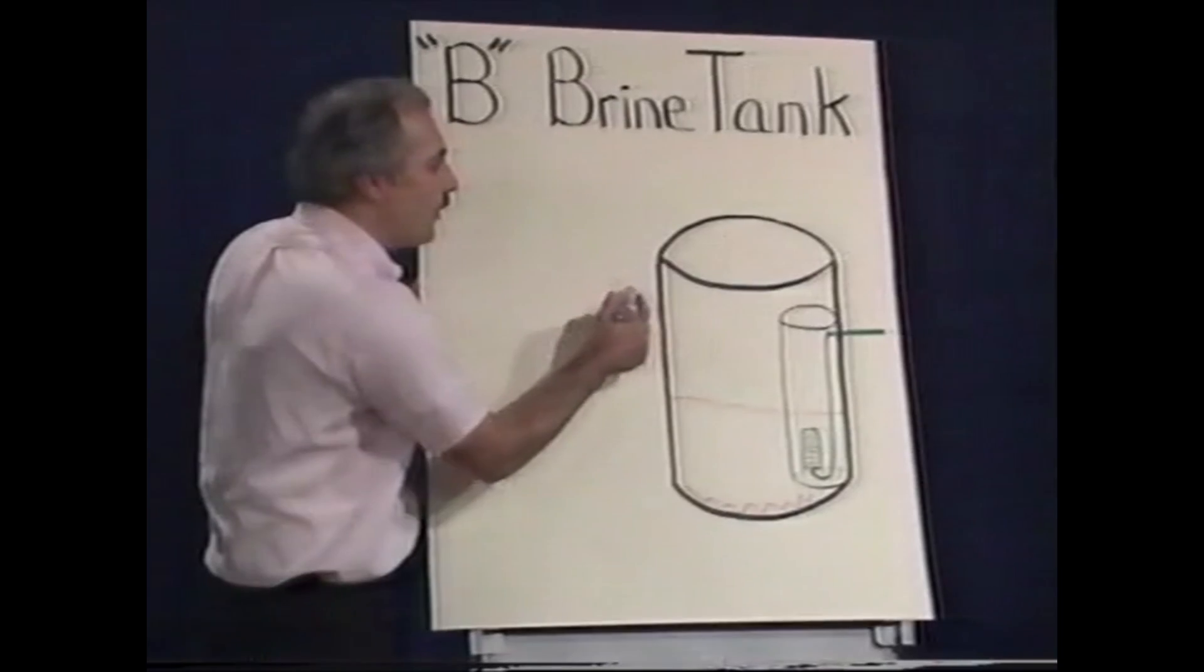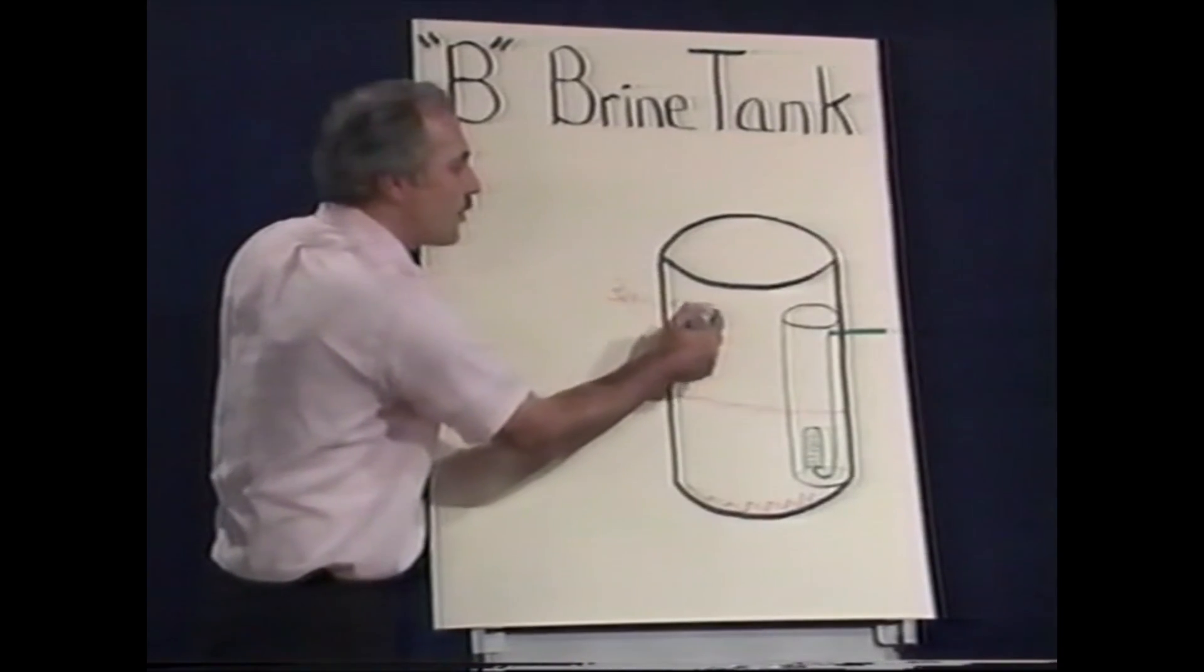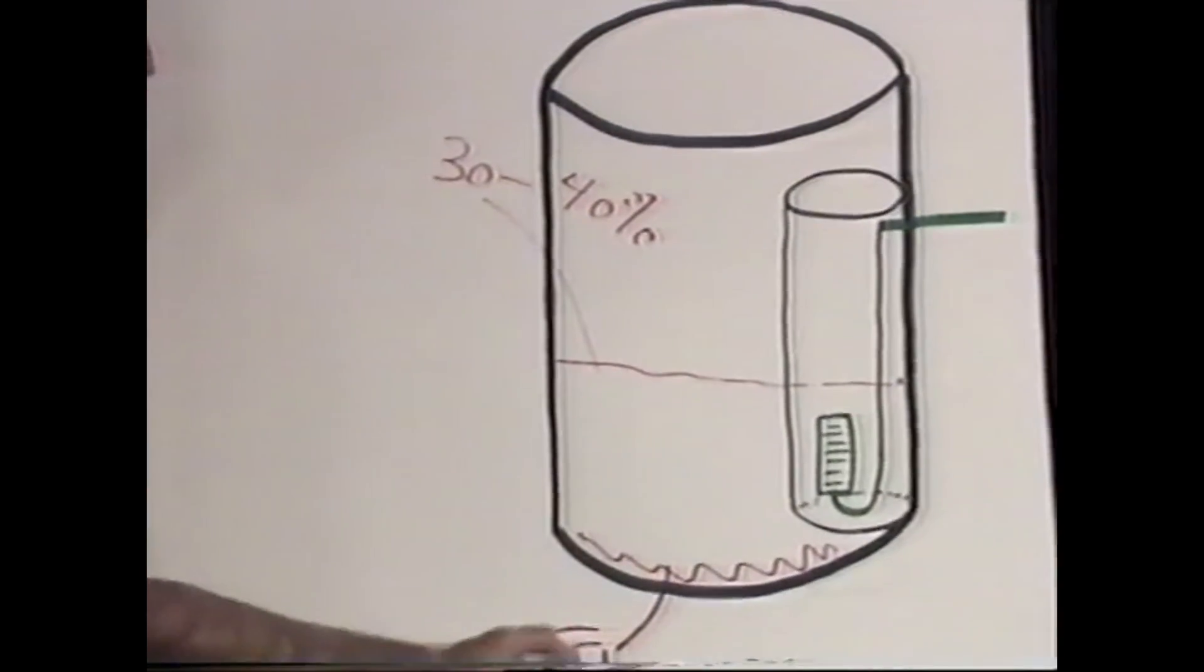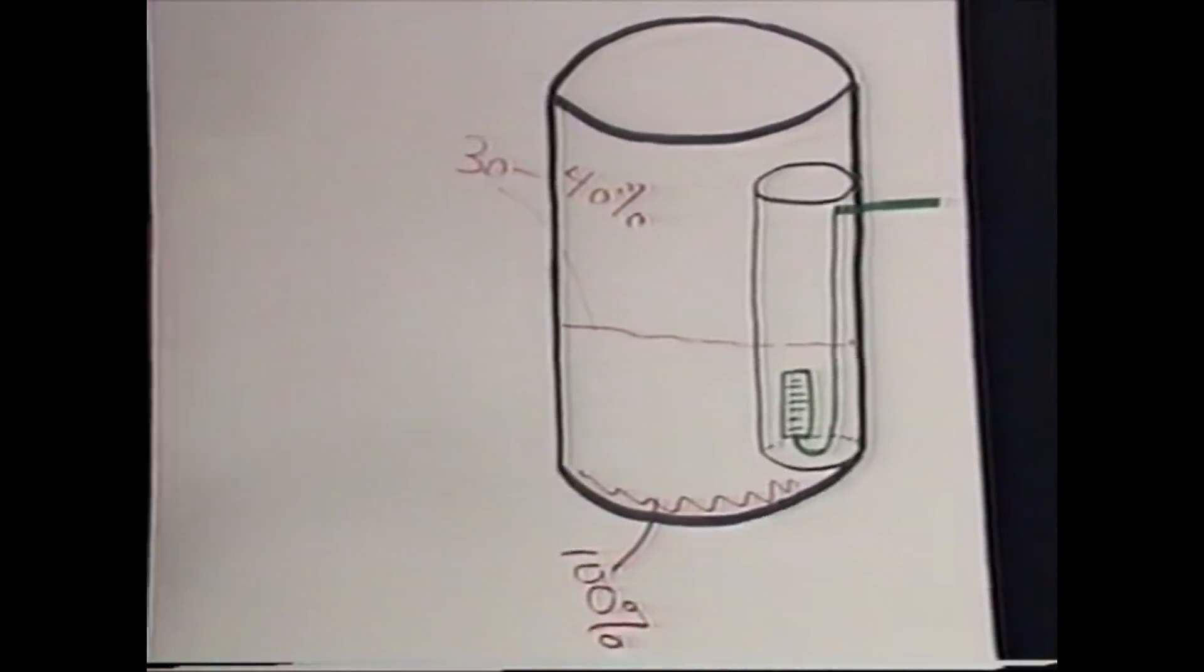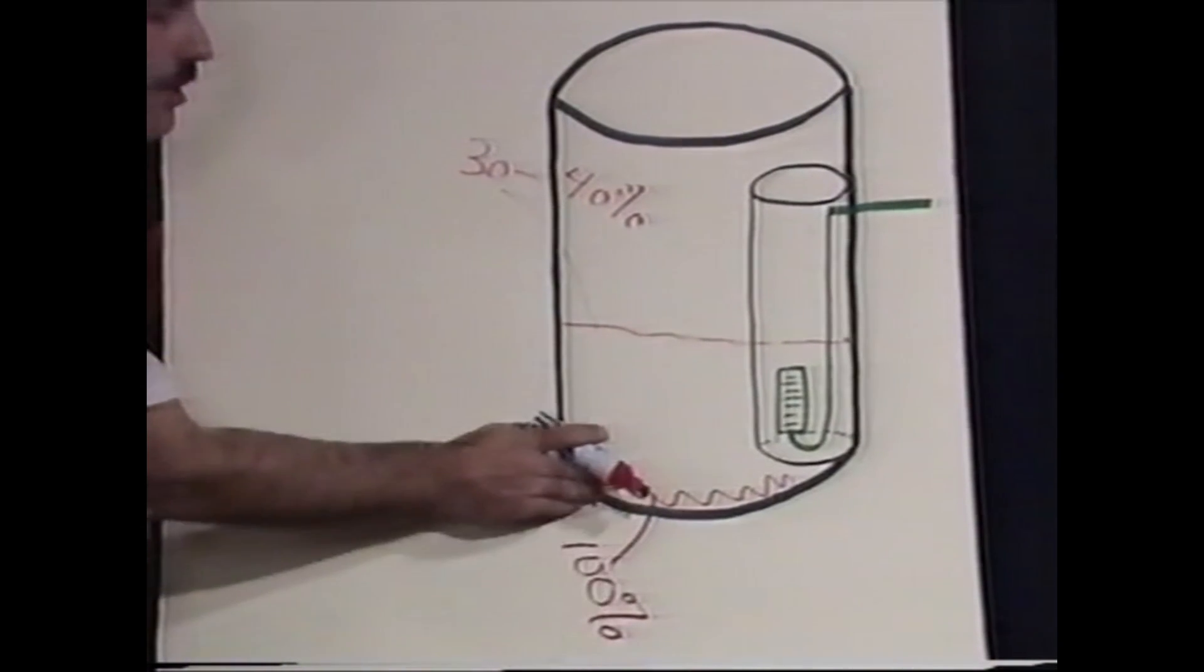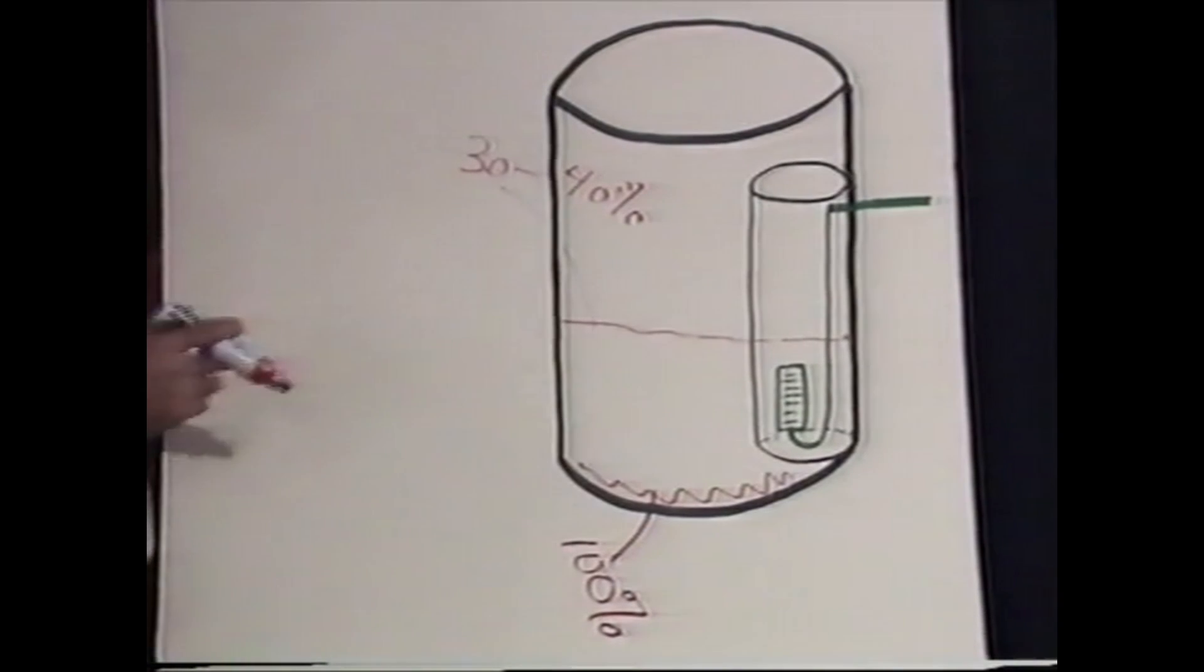If you siphon it right off the bottom, you have 100% concentrated brine. You're basing all your regeneration capacities on 100% brine. That salt level has to be above the water level.